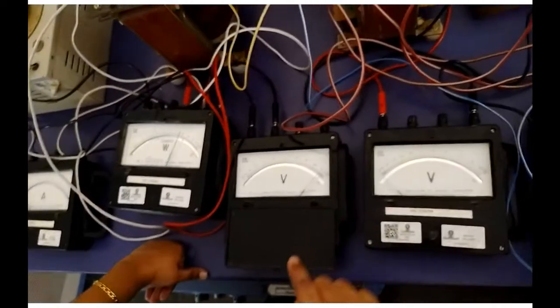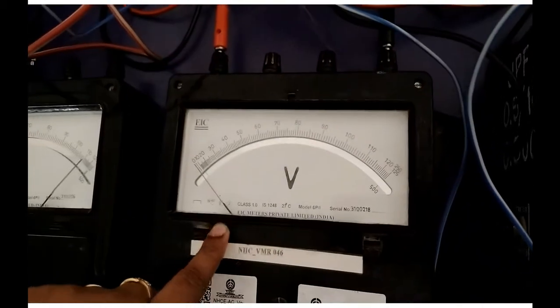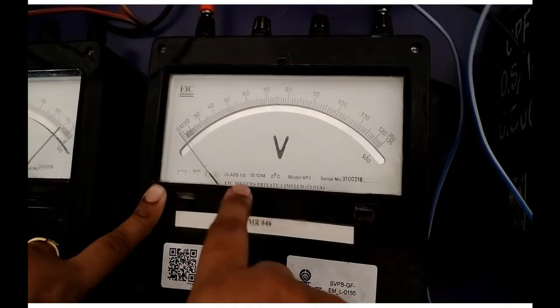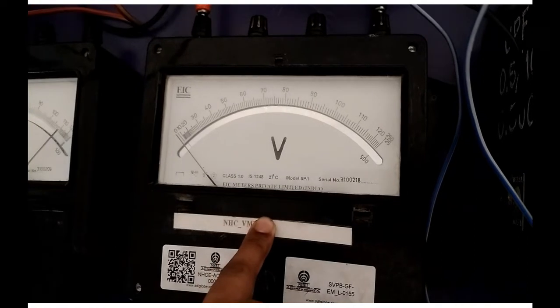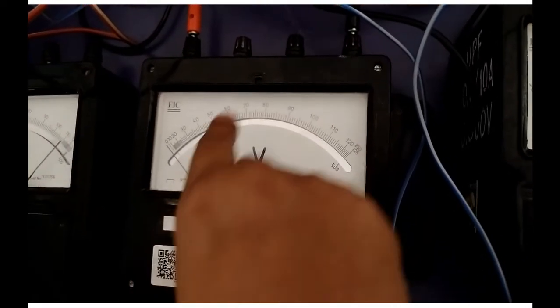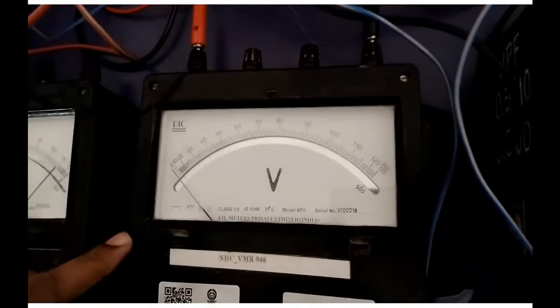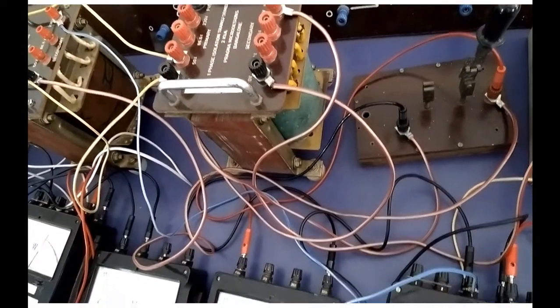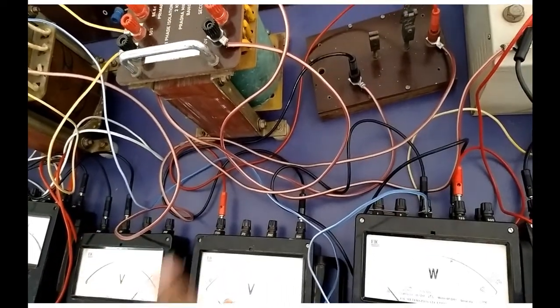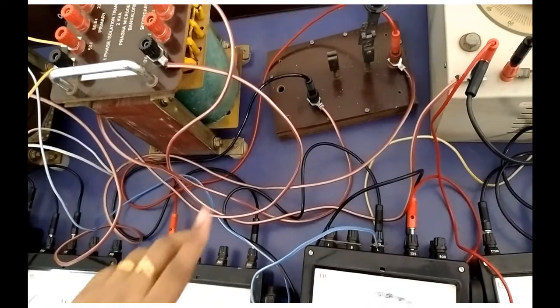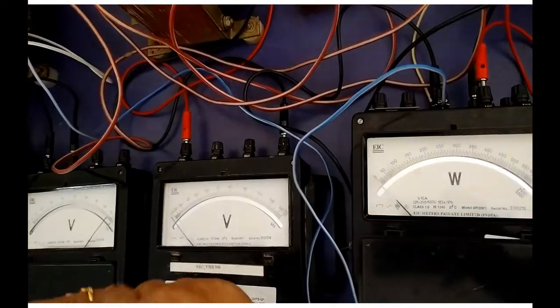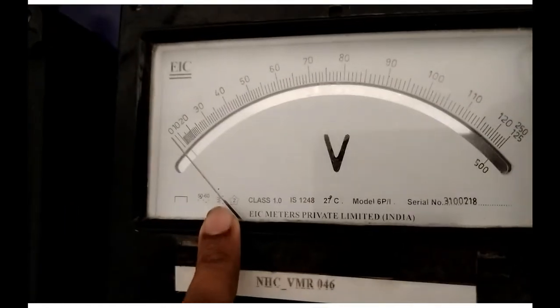These are the open circuit measurements, right? The other important thing is that across the SPST switch we have connected a voltmeter, and we have to check its value. Usually the voltmeter should read 0. Only then is the polarity of the secondary terminals of the transformers correct. If it is not proper, the voltmeter will read double its value. So before closing the SPST switch, make sure the voltmeter reads 0. If it is not reading 0, you have to change the polarity of one of the HT terminals. If the reading is 0, the polarity is correct and you can close the SPST switch. Here you can see the voltmeter is reading 0, so we are closing the SPST switch and we are going to perform the SC test on the other side.